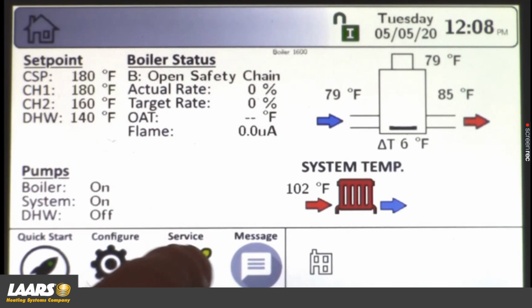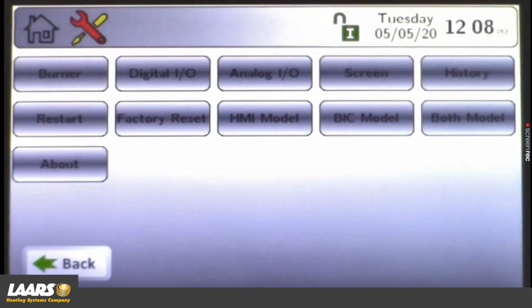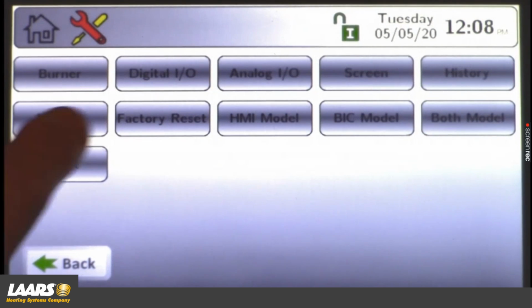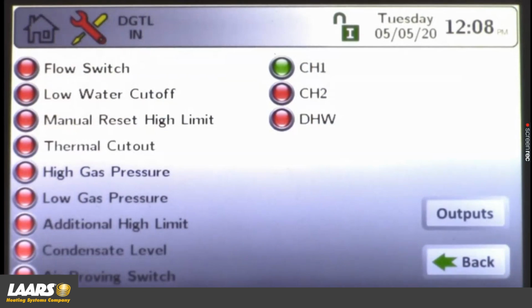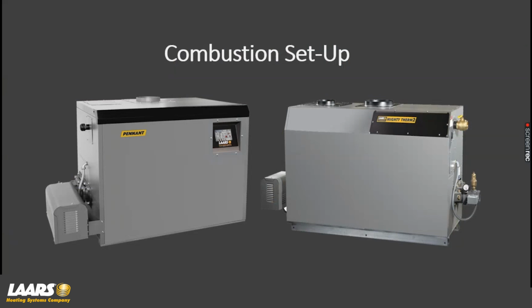Let's go under service, and there's some options here for service. For technicians or starting up a boiler, a commissioning agent, go to Digital I/O. And this is your sequence of operation for your safety devices, such as flow switch, low water cutoff, etc. Whatever is in red, that's where you've lost power, or that's where your device is open. An example, if I make the flow switch, now everything is made, and now we're actually going into ignition or pre-purge.